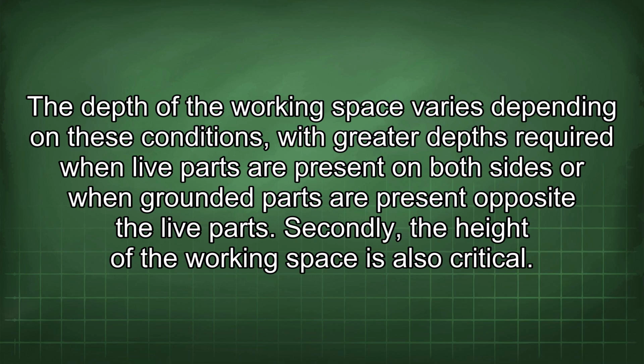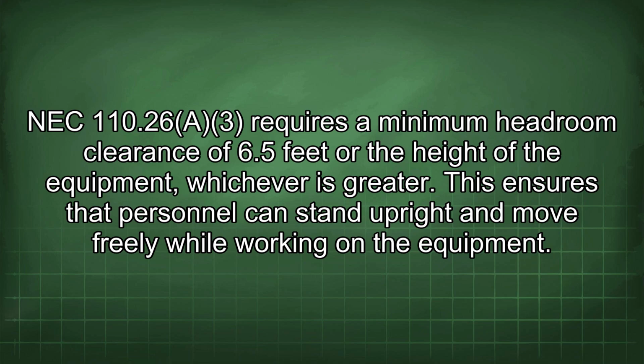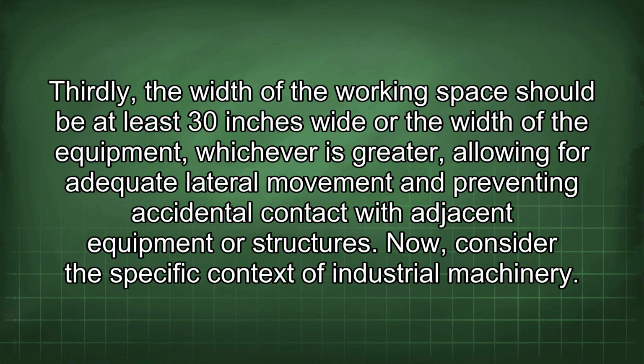Secondly, the height of the working space is also critical. NEC 110.26(A)(3) requires a minimum headroom clearance of 6.5 feet or the height of the equipment, whichever is greater. This ensures that personnel can stand upright and move freely while working on the equipment. Thirdly, the width of the working space should be at least 30 inches wide or the width of the equipment, whichever is greater, allowing for adequate lateral movement and preventing accidental contact with adjacent equipment or structures.